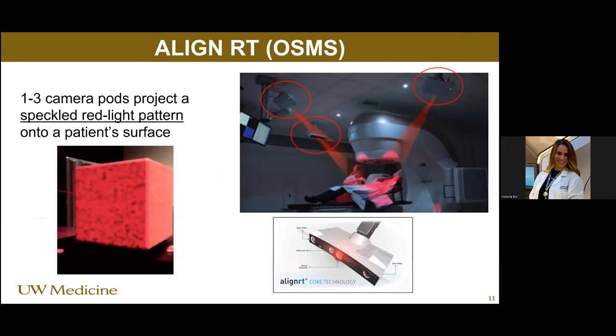The next commercial system is the AlignRT system, also previously called OSMS — Optical Surface Monitoring System — by VisionRT. It also uses one to three camera pods, but rather than using structured light, it uses a speckled red light pattern projected onto the patient's surface. Three cameras are similarly mounted to the ceiling of the treatment room above the linear accelerator.